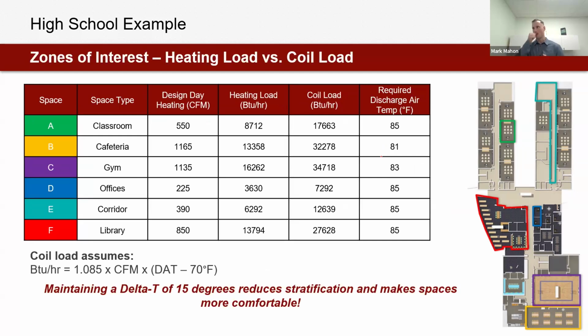And then this is a really important step. Once again, just kind of math on paper for us here. But the difference between the heating load for the zone and the coil load, the actual coil capacity here, is a very different constraint and a different performance characteristic for the building. If our heating load for the classroom here is 8.7 MBH, what we're actually going to need from a coil load perspective is 17.6 MBH.